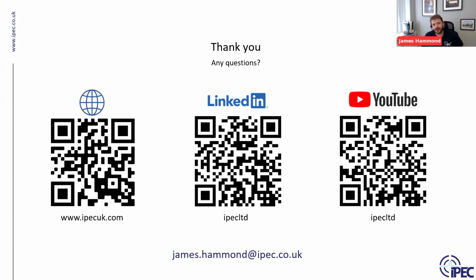Yeah, definitely. Those environmental conditions are a huge factor as well because they're changing constantly. I've done PD testing at certain times of day and it's changed - different from before - because there are so many external factors that cause PD to increase. Could be humidity, temperature, as you say, particles, dust. A lot of our installations are actually in Saudi Arabia, where there's a huge amount of sand and dust particles, and we see quite a clear correlation between areas of higher dust or wind activity, where there's more sand, and higher partial discharge. And again, coastal areas where there's salt in the air make a huge difference that you only really know once you start actually doing these tests. Then from that data, you can plan accordingly, which is one of the main points really.